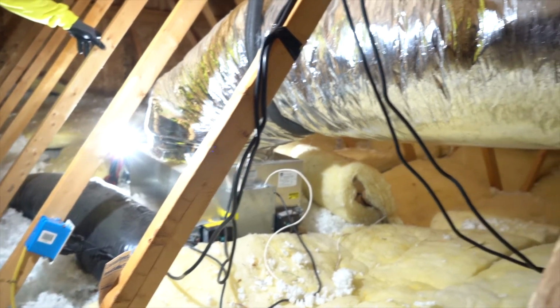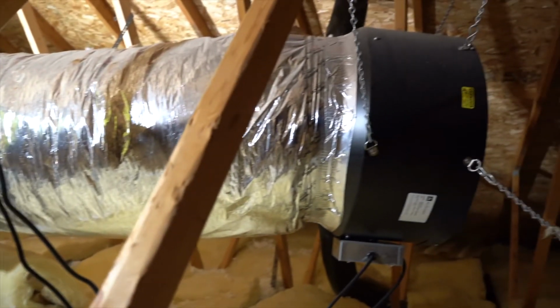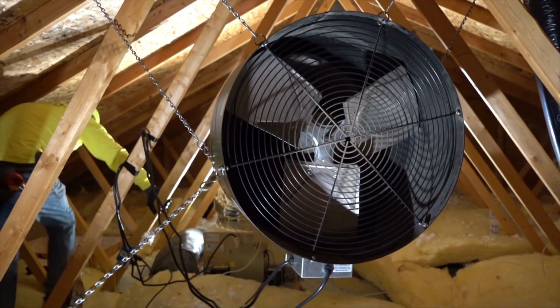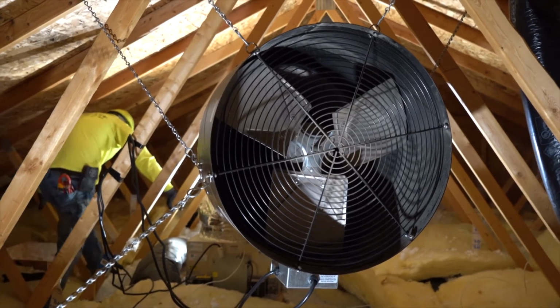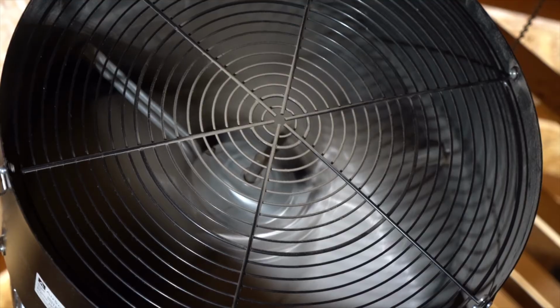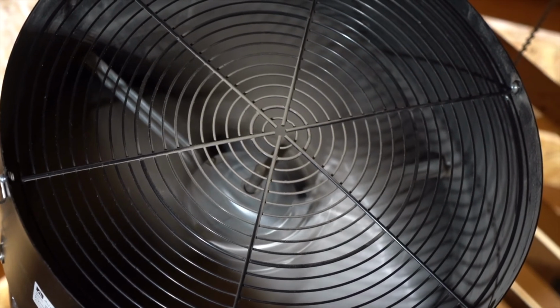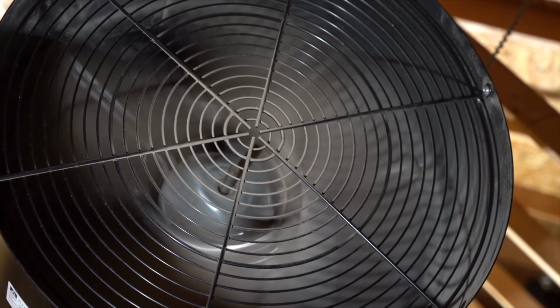One of the other big cost factors is a direct-driven fan versus a belt-driven fan. Of course, a belt-driven fan has the motor off to the side, and the fan itself is attached through a belt and pulley. Those are usually a lot less expensive, but much noisier. The direct drive ones have the motors attached directly to the fan.